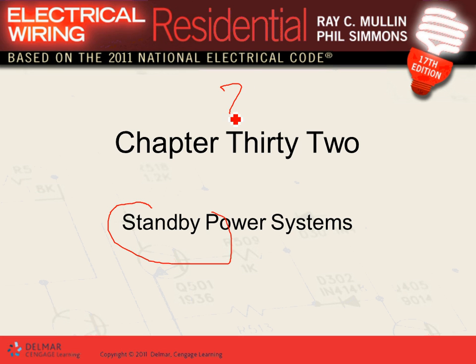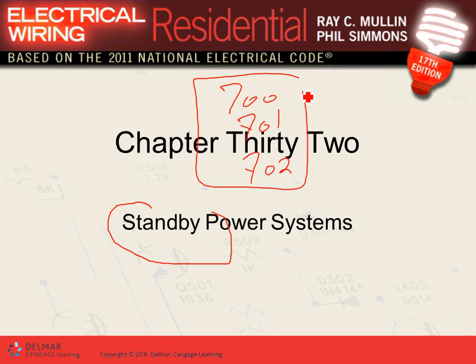There's Article 700, Article 701, and Article 702 in the NEC code book that talk about the emergency system, legally required, and optional systems. These are the emergency system, legally required, and optional, and this will apply to all of them.